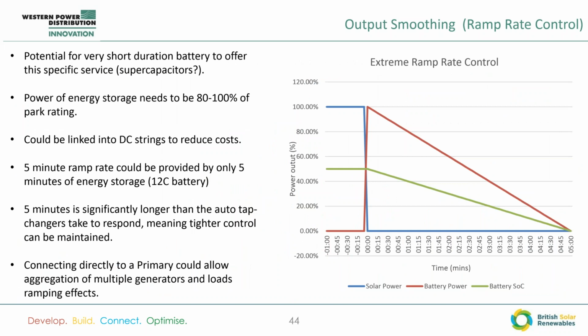Ramp rate control, however, doesn't have to cost nearly as much as the other use cases, because you need a very short duration battery to be able to offer this particular service. It needs to have high power, 80 to 100% of park rating, because you can get 80% drops in irradiation on cloudy days. It could even be linked into DC strings to reduce costs, because it's just moderating the export. And a 5-minute ramp rate can be provided by only 5 minutes of energy storage that's waiting at 50% to be able to offset whether it's an increase or decrease.